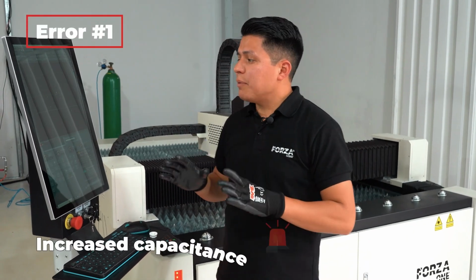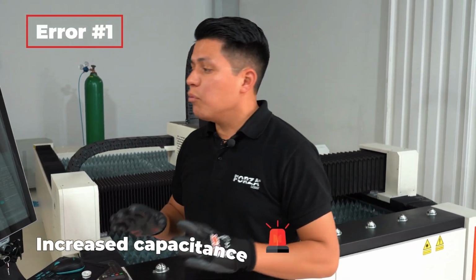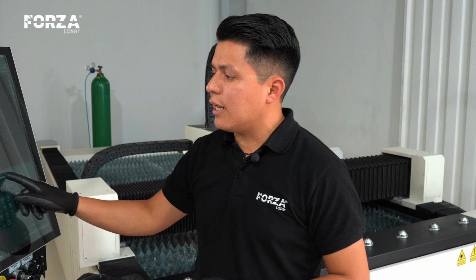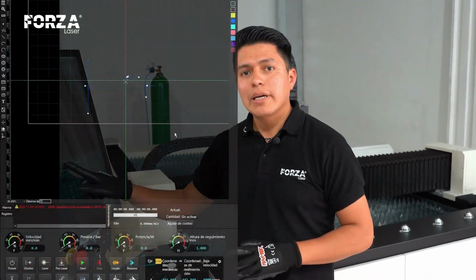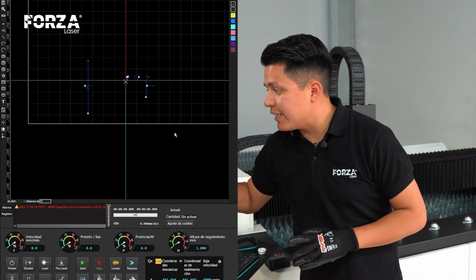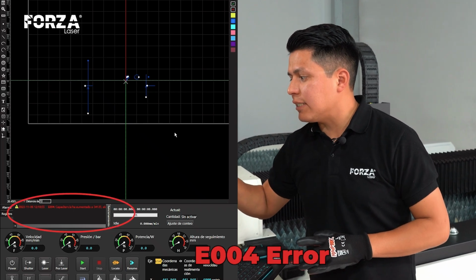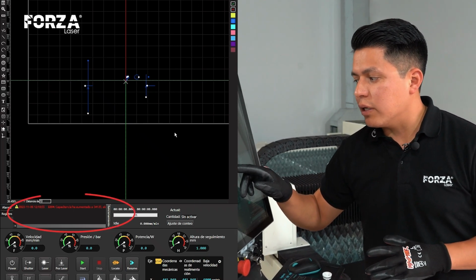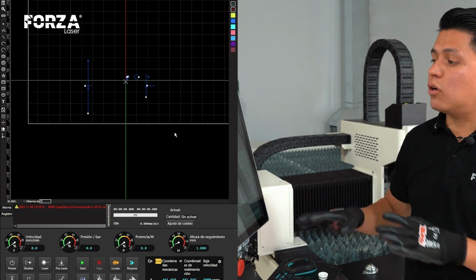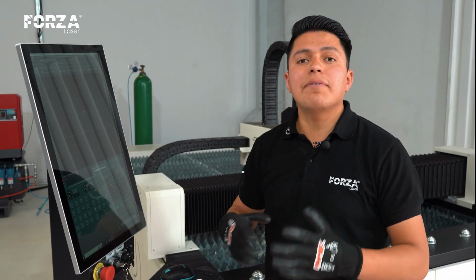Let's go with error number 1. The first error is increased capacitance, and it shows up in the alarm section something like this. This is error E004, which indicates increased capacitance at 54,135. This value is different for each machine.